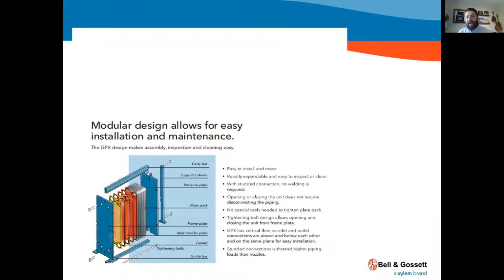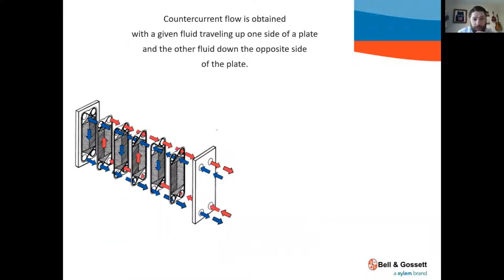At the back, you've got the pressure plate. This one actually slides on the rail. It's a bigger, thicker one you can see there. I don't think you can see my mouse, no. So that's your plate in the back, the pressure plate, and that's applying the pressure, keeping everything tight. You can get the connections on these on the front there, as you can see, a number of ways. You can get them threaded, studded, or flanged. The important thing is that when you bring your pipe in, you pipe with counter current flow.